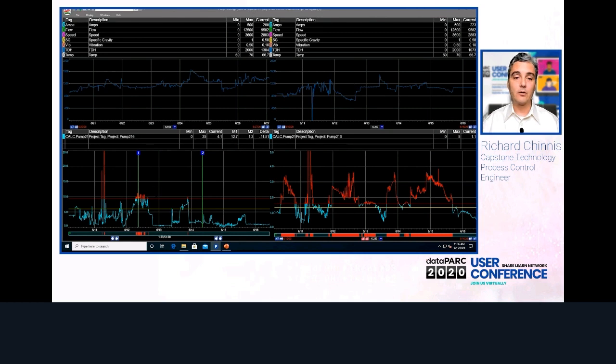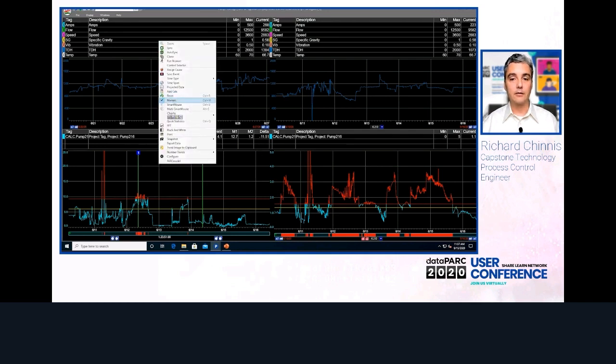So that is the reason that this has gone above the limit, so to speak. The model is basically saying, you know what, I'm okay with the total dynamic head getting to a certain point below 923, but once you get down too far, I'm going to start saying the extrapolation is now questionable. So the Hotelling T2 is telling you about range. Now what about the D mod X? There's a lot more red on the D mod X.